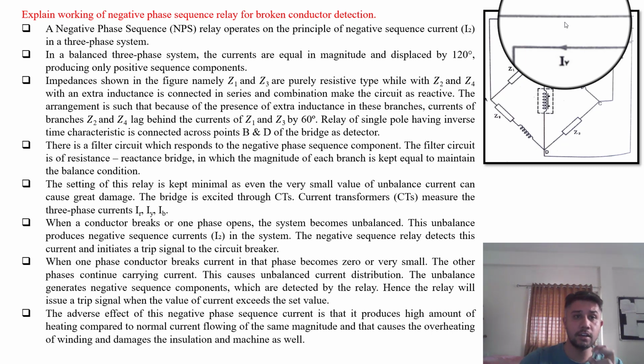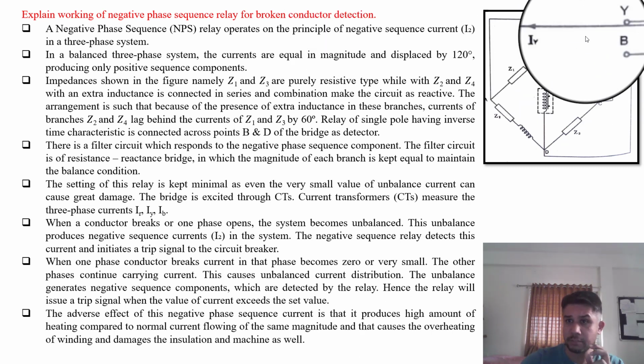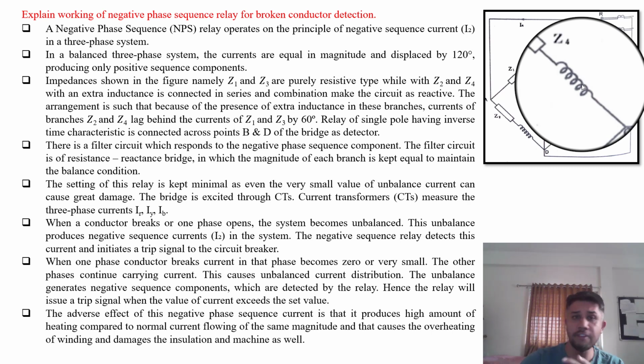Explain the working of a negative phase sequence relay for a broken conductor detector. Earlier we have seen the functioning of the negative phase sequence relay. A similar arrangement is shown for the three-phase broken conductor detection scheme for a transmission line or for a distribution cable.